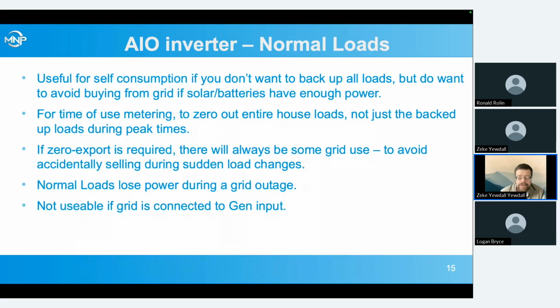This can be useful if you don't want to back up all your loads, but you do want to be able to use as much solar as possible and batteries rather than exporting to the grid. Maybe you have a zero export system where you're not allowed to sell to the grid, or maybe it's just a really unattractive selling rate. You can essentially use more solar power than just what would go to the backed up loads without just selling it to the grid and buying it back at night.